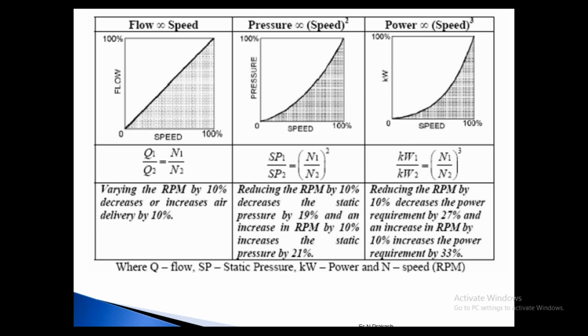To overcome the resistance only, the pressure is given for the fan. Whether it has been taken care of while the design itself is having high pressure or not. If you replace the fan with a low pressure fan and again change the speed, it will be giving the CFM, but it will not have enough pressure, and it will not reach the tail end of the department. So there will be uneven hot pockets. We are facing hot pockets in the production hall due to this reason.